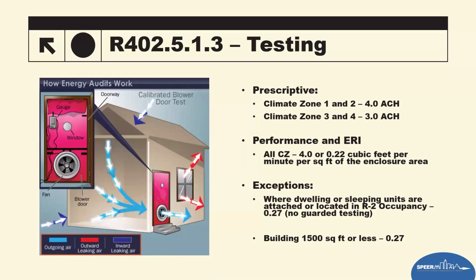So there are exceptions that are still there. This came in the 2021, but if you're not familiar with that, they've now addressed it to where dwelling and sleeping units that are attached like apartments, you can do 0.27 CFM, but that cannot be a guarded test. In other words, you cannot do blower door on both sides and just do the one in the middle, which used to be allowed by code. It's no longer allowed. It's going to be a standalone non-guarded test. And then lastly, any building or home or dwelling that's less than 1,500 square feet can now use the CFM per square foot of enclosure area, and the 0.27 is the requirement. No longer are you trying to hit an ACH. That's really tough to do in homes or buildings that are less than 1,500 square feet.